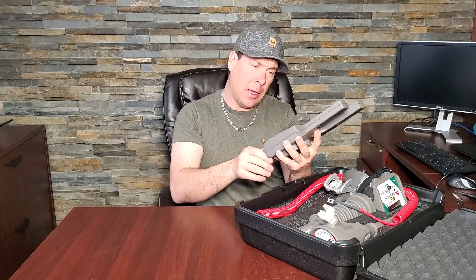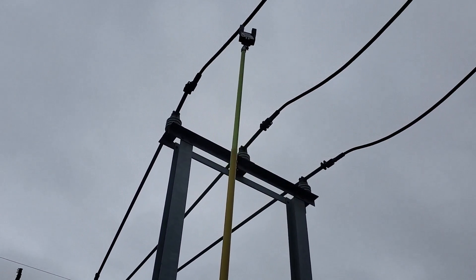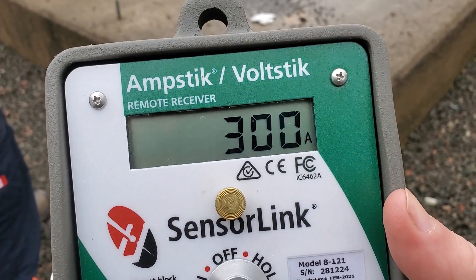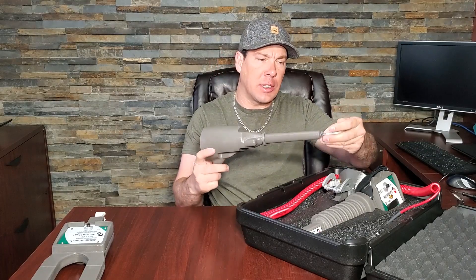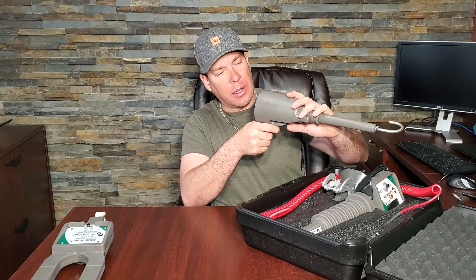Let's head inside for a minute. The first item in the Troubleman's Kit is the amp stick — radio transmitted amp stick. It's good for high voltage, rated up to 69,000 volts, and 1 to 5,000 amp auto-ranging. Very cool. It's reading 300.